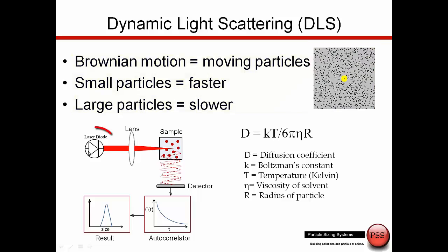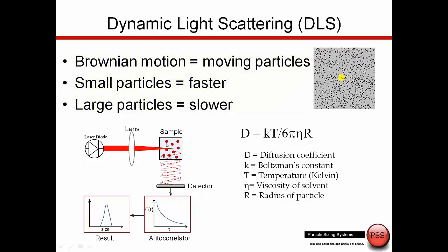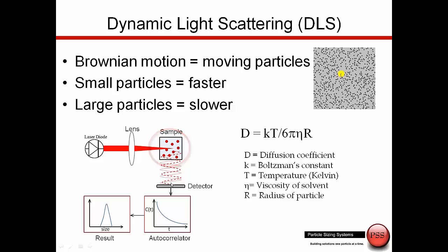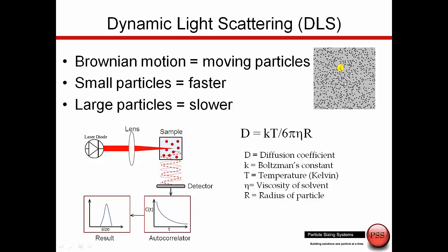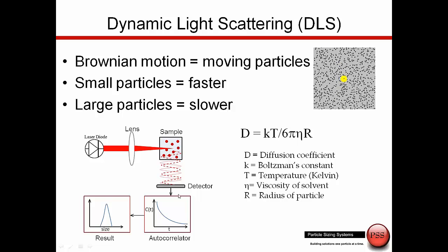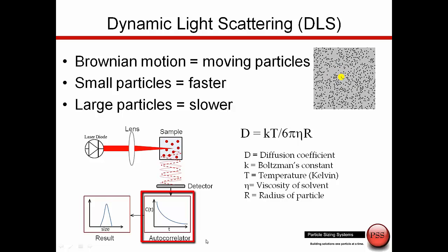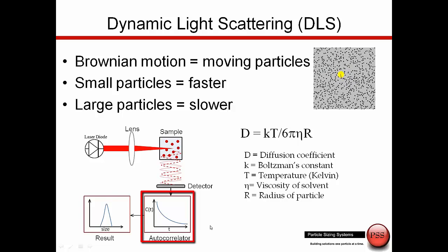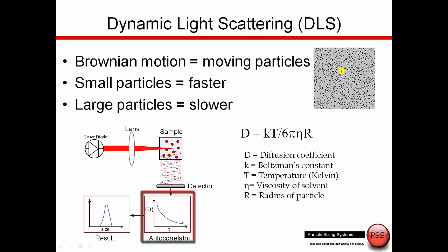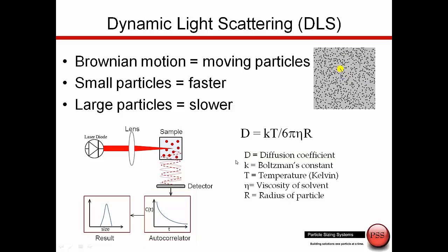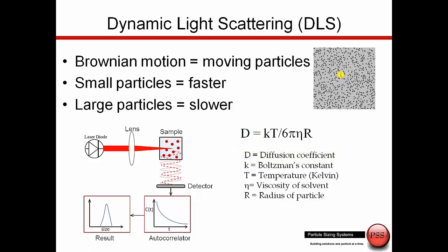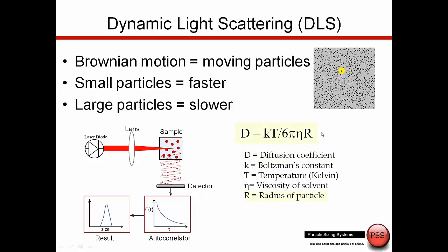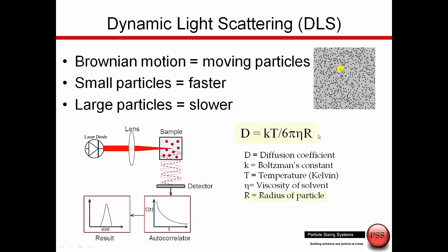With dynamic light scattering, we have a light source, the sample sits in a cuvette, and we have a detector. We look at the light scattering due to the Brownian motion of the particle. This creates a correlation function. From the correlation function, we extract the translational diffusion coefficient D, and then use the Stokes-Einstein equation to calculate our radius.